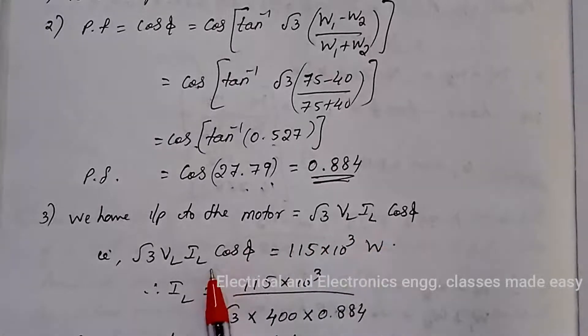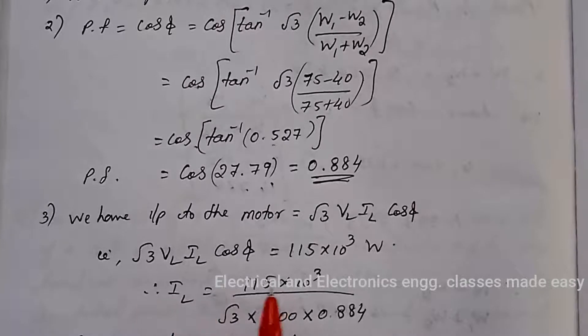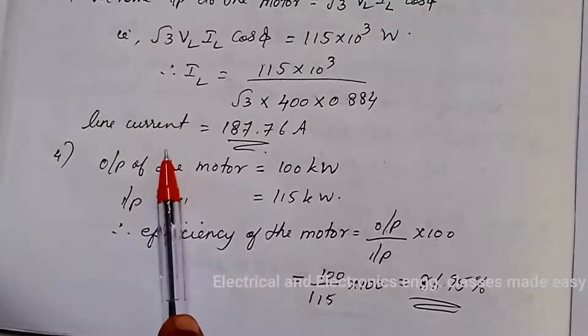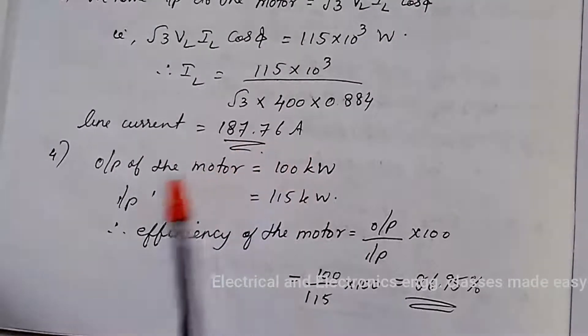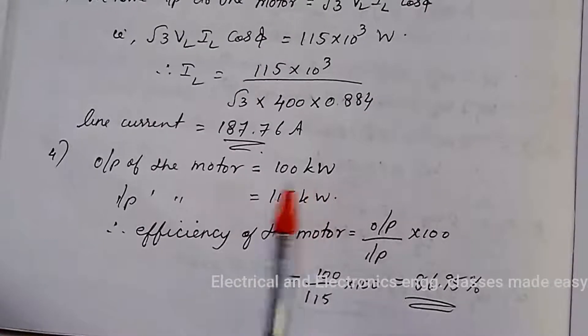Since the input = √3 × VL × IL × cos φ = 115 × 10³ watts, we can find the line current: IL = (115 × 10³) / (√3 × 400 × 0.884) = 187.76 ampere.